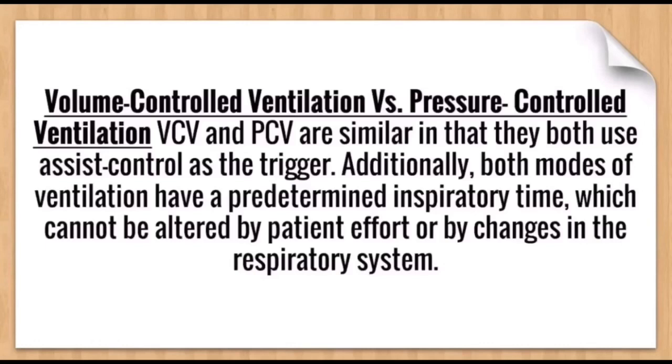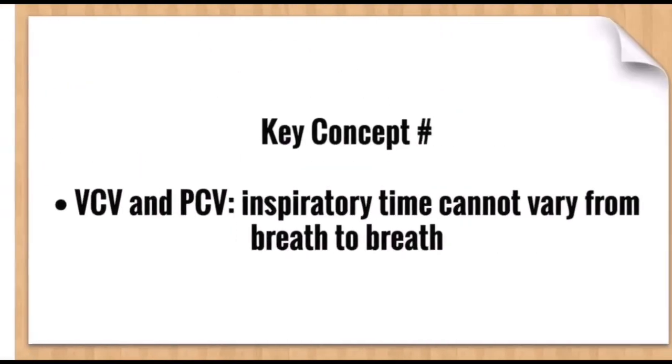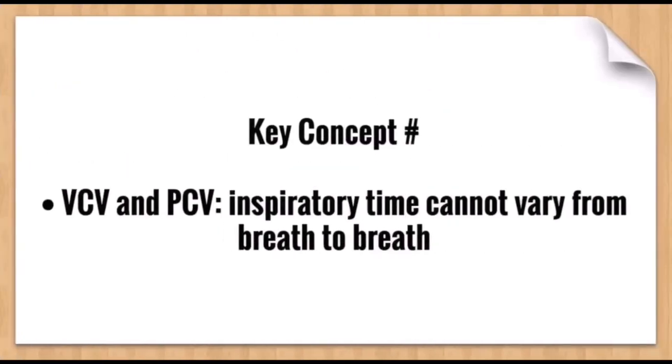In pressure control, we directly set the inspiratory time. In volume control, inspiratory time is indirectly set by the flow and the volume. Now in pressure control, as I said, the inspiratory time is directly set, and in volume control, inspiratory time is determined by setting flow and tidal volume. Now key concept: in pressure control ventilation and volume control ventilation, inspiratory time cannot vary from breath to breath.